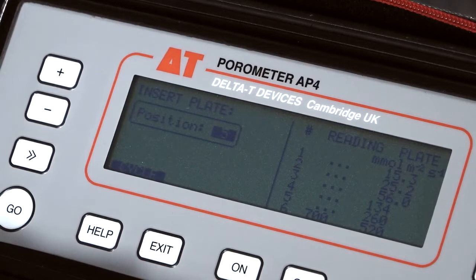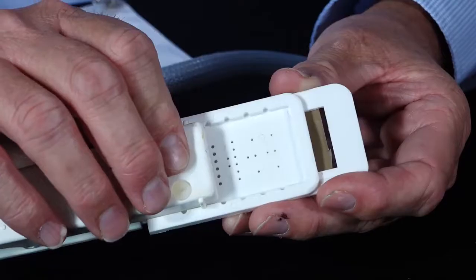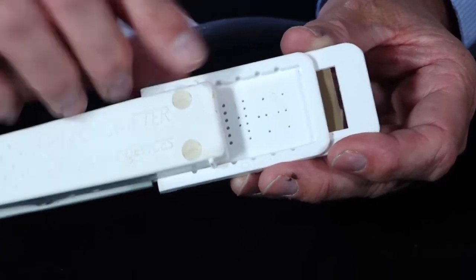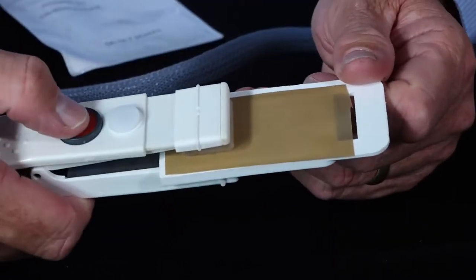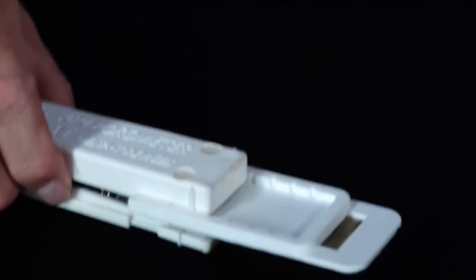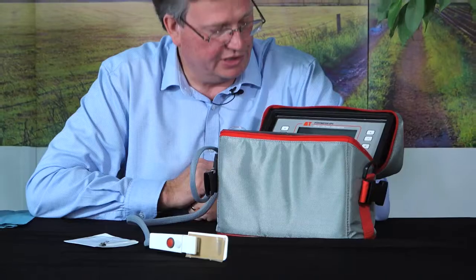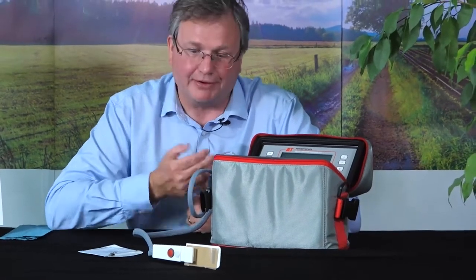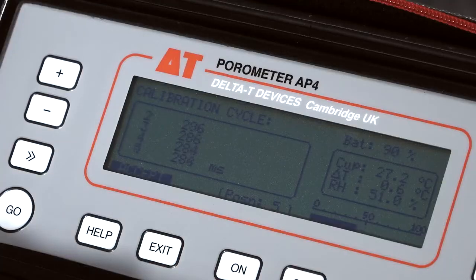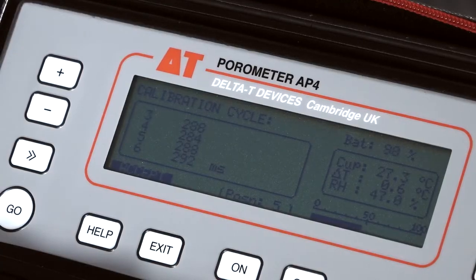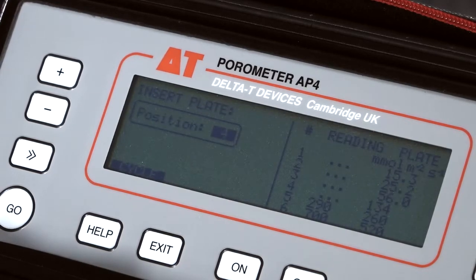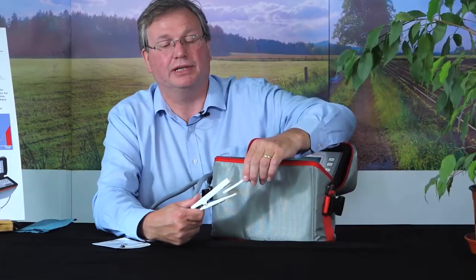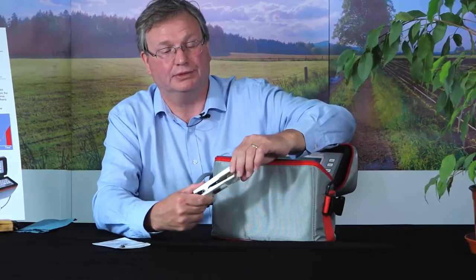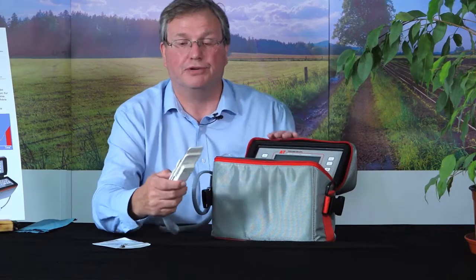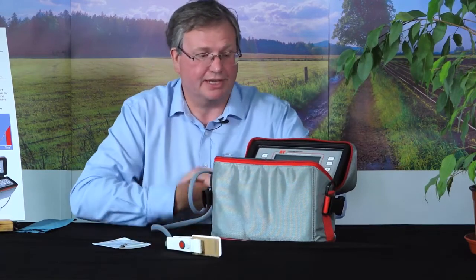So just as before, we'll unclip and reclip the head at position 5, make sure it's located correctly, press the red button and put it on the desk. And again, we're waiting for this double beep, which we've got already. It's very fast because the holes in the calibration plate here are quite large. So we'll accept that calibration reading. We're prompted to go to position 4. So the holes in the plate are getting steadily smaller. And we go to position 4, press the red button, place it on the desk and wait again.